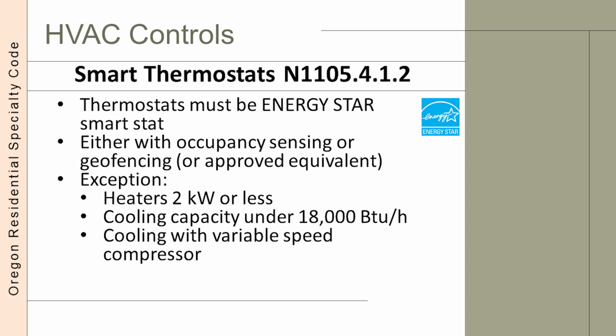Moving forward with mechanical requirements, one new 2023 ORSC item is for the use of smart thermostats. The requirement is to have an Energy Star smart thermostat. In addition, the thermostat must be capable of either occupancy sensing or geofencing. Geofencing senses when the occupant is not at the site through signals from a phone or otherwise. The building official can also accept an approved equivalent. Technology is changing quickly and alternates should be available for consideration.